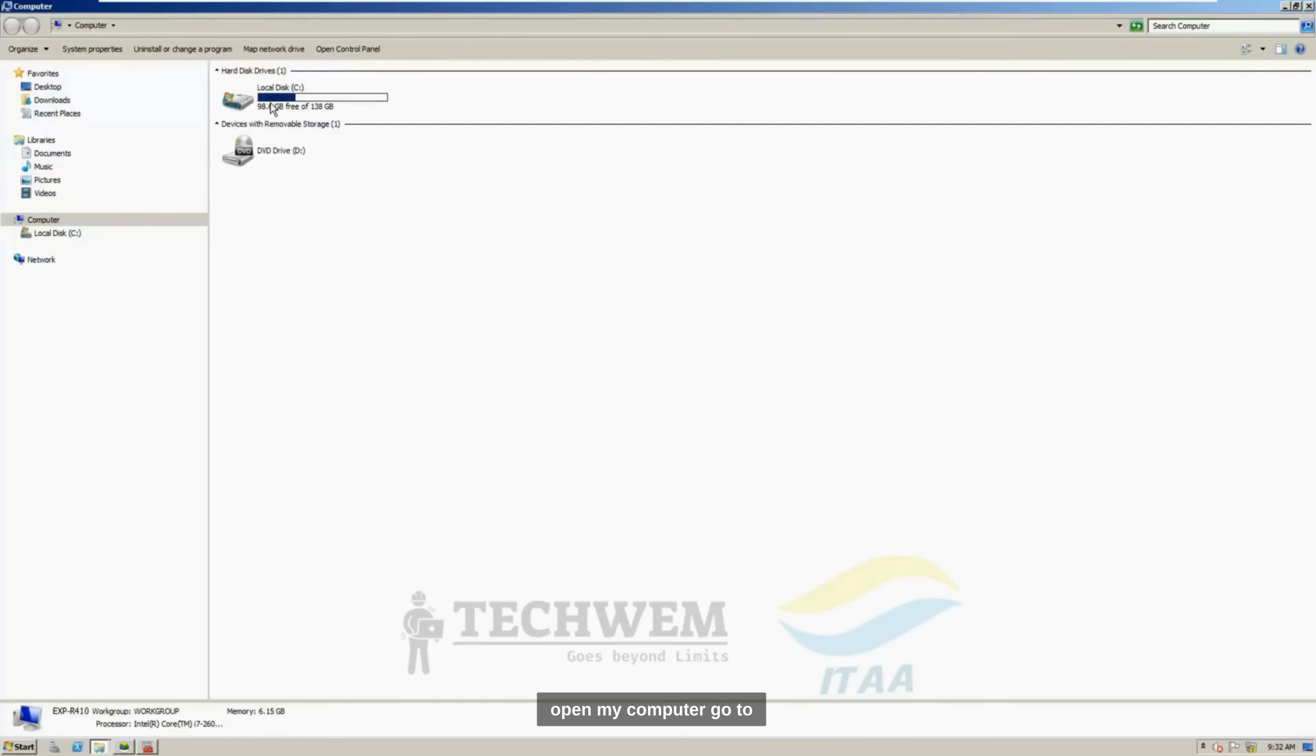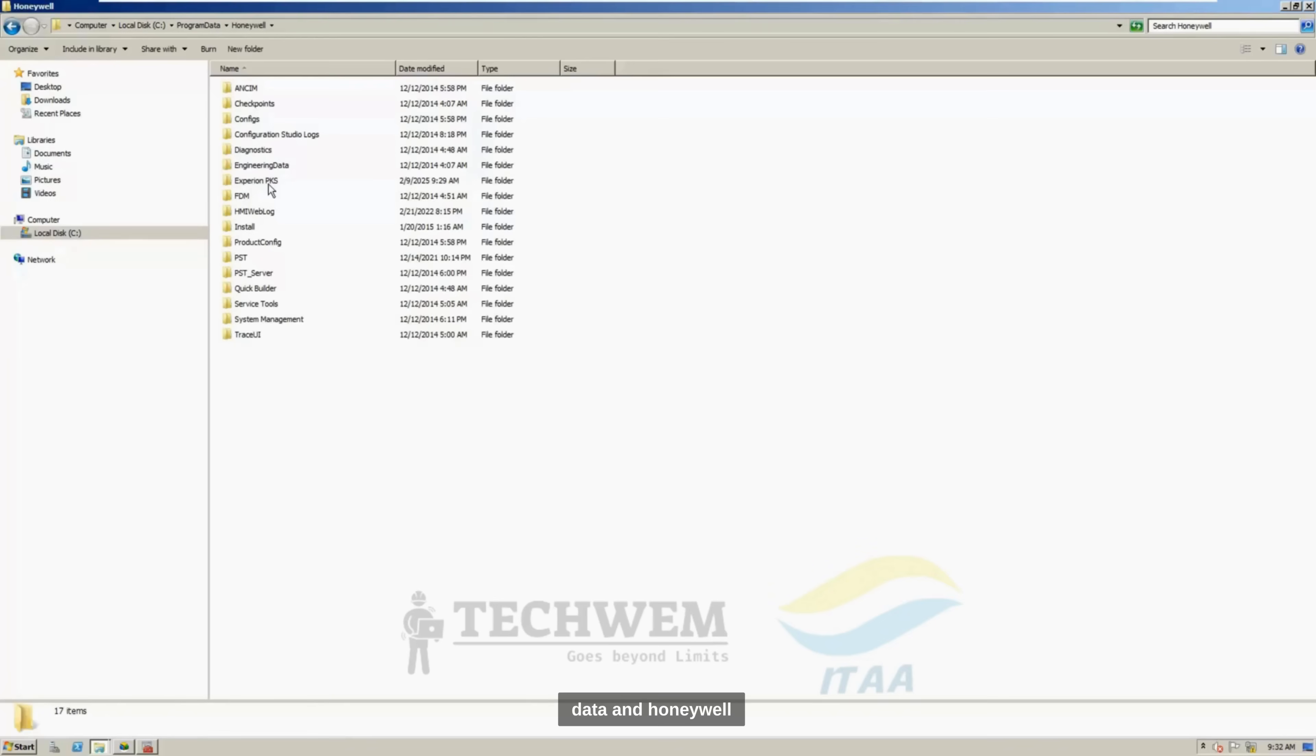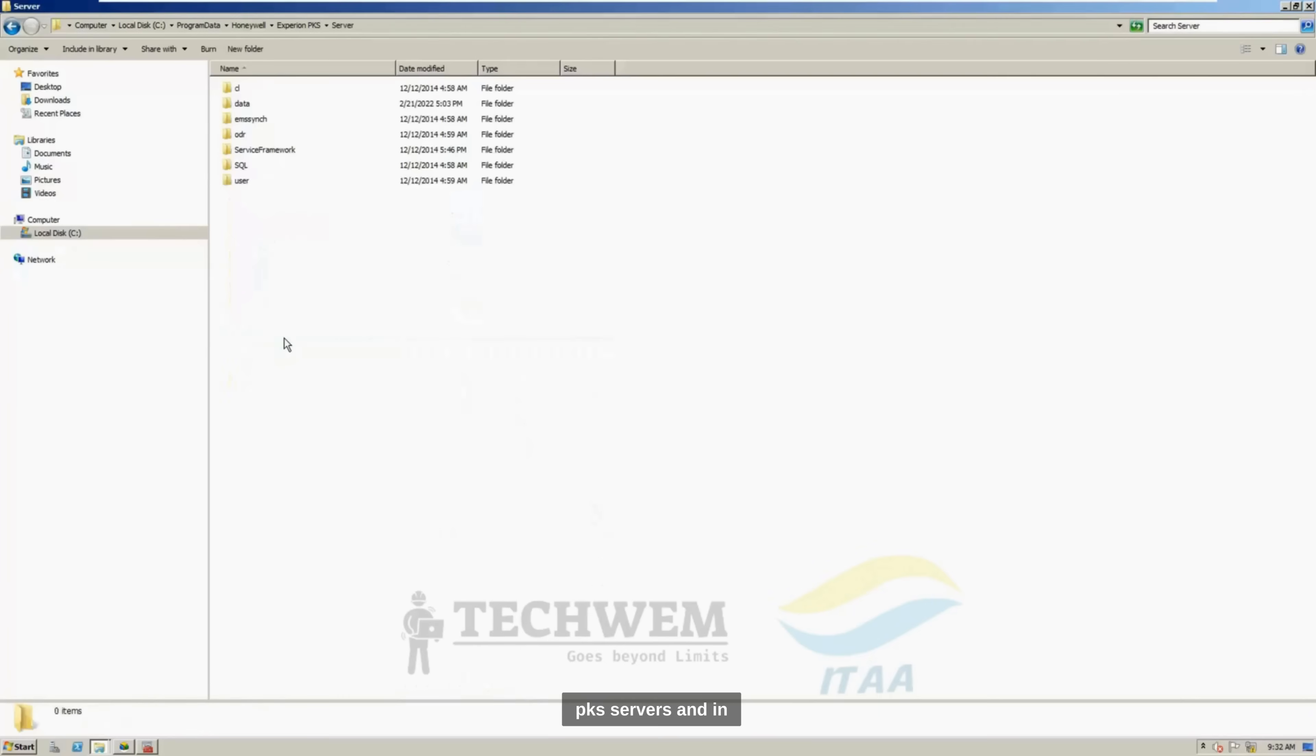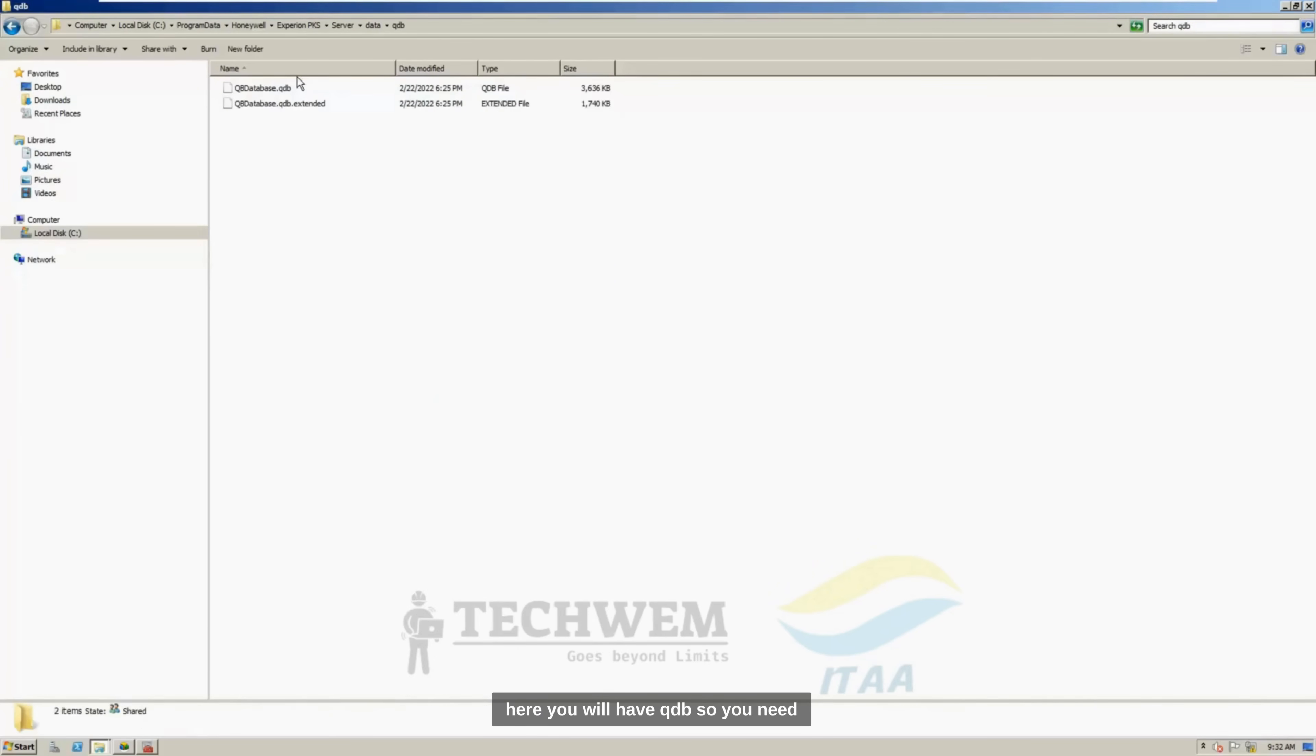Now, for the Quick Builder Database, sometimes you can call it SCADA Database as well. Now, to start taking backup for Quick Builder, open My Computer, go to C, click on Program Data, and Honeywell, here you can find out Experion PKS, Servers, and in Server, you will find Data, and here you will have QDB.